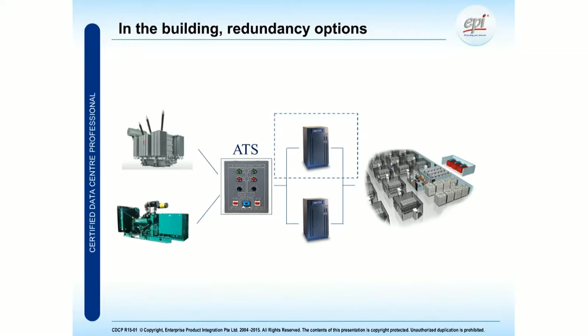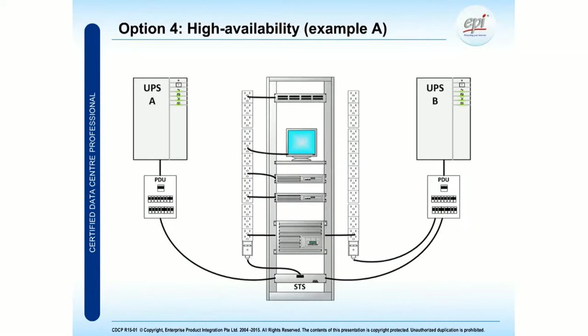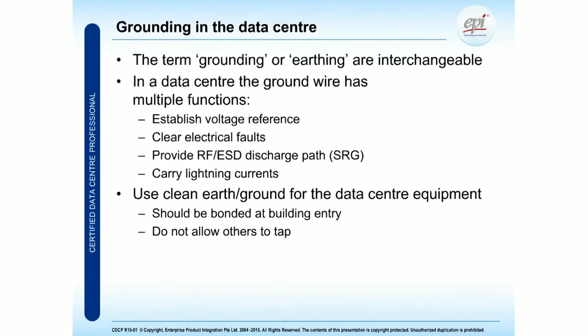So the IT equipment should not suffer from downtime. We have many examples in the CDCP talking about redundancy as well. This is another example based on rack level, where we provide two separate power feeds to the server rack, and we connect both power feeds to a static transfer switch, which is installed at the lower part of the server rack, an A and a B feed, and it will create one feed to the IT equipment, both A and B. In case UPS-A or UPS-B fails, stops working, or needs to be maintained, the IT equipment will still be provided with power inside the rack. So this is one of the many different high availability examples that we talk about and list inside the CDCP course as well.